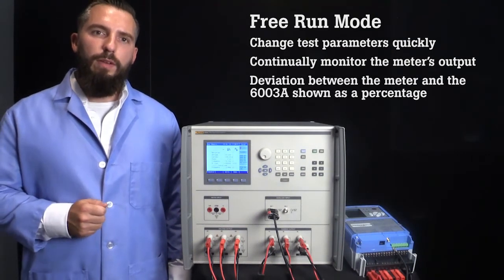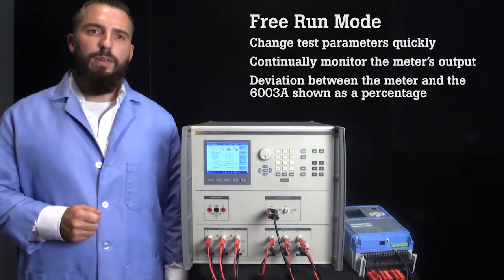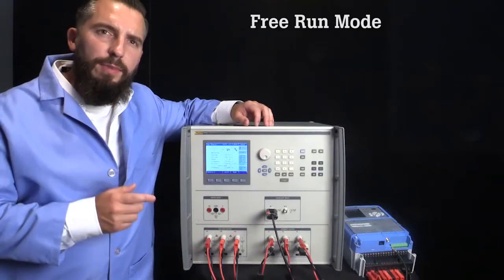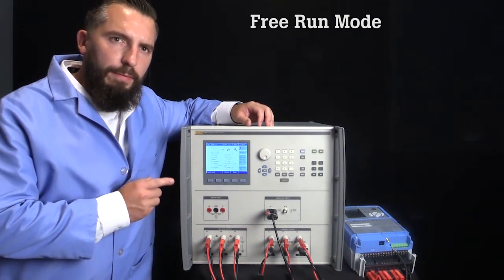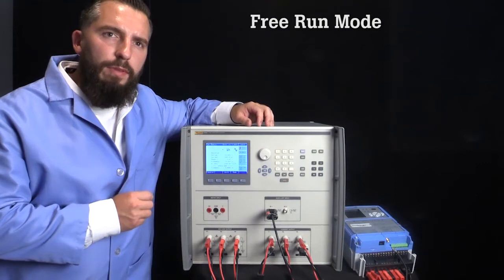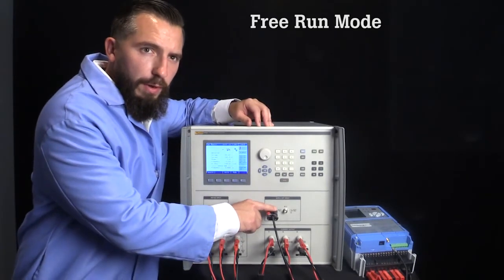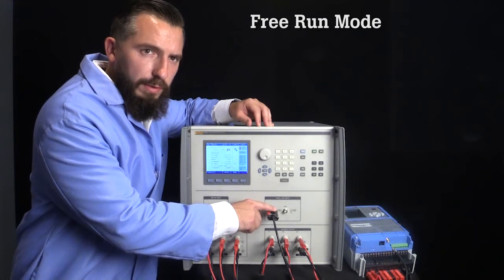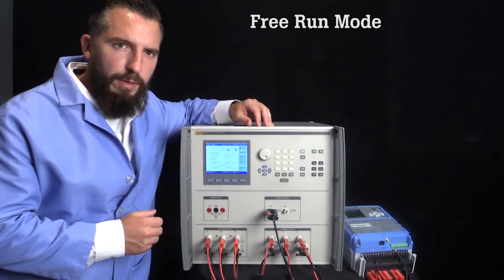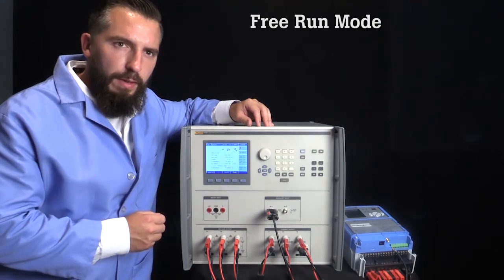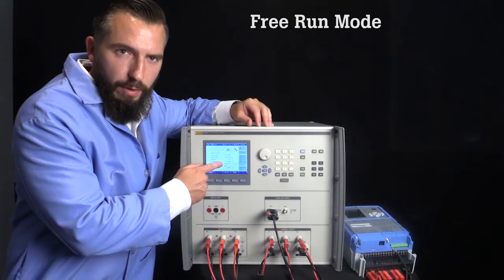Free Run allows you to quickly change the test parameters by continually monitoring the meter's output to verify that the correct meter constant is being used. The deviation between the meter and the 6003A is continuously calculated and shown as a percentage on the display. To demonstrate, I've configured a test for 200 volts AC, 1 amp, at 50 hertz. Since we'll be measuring the pulse output of the meter, I've connected the pulse output of the meter under test to input 1 of the 6003A.